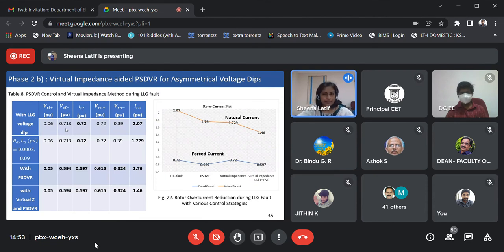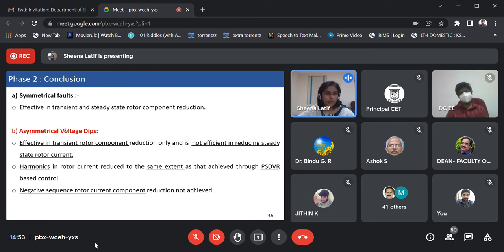A graphical representation of natural rotor current and forced current reduced by different methods is plotted, and it shows that the natural current is reduced by the virtual impedance control strategy from 2.07 to 1.46, the combined effect of PSDVR and virtual impedance control strategy, while in the forced current, it is the PSDVR action still sustaining, whereas the virtual impedance does not have a serious contribution.